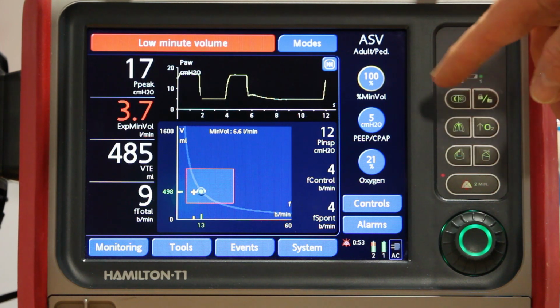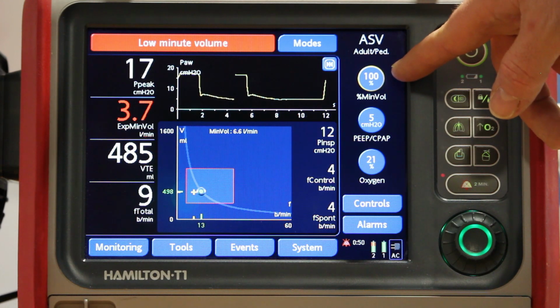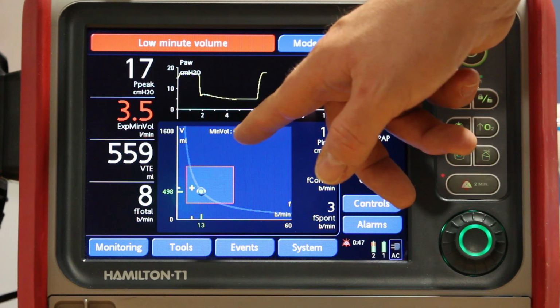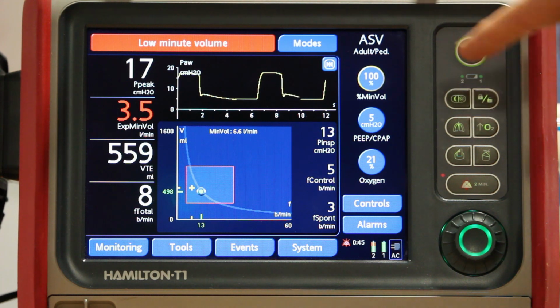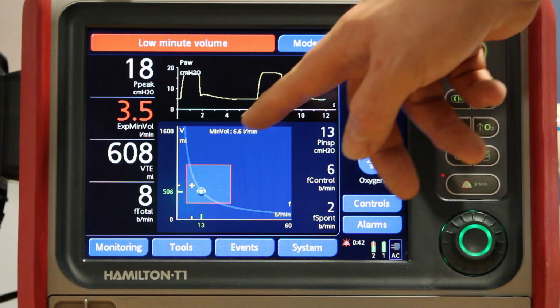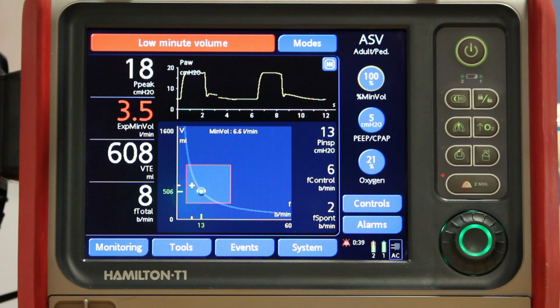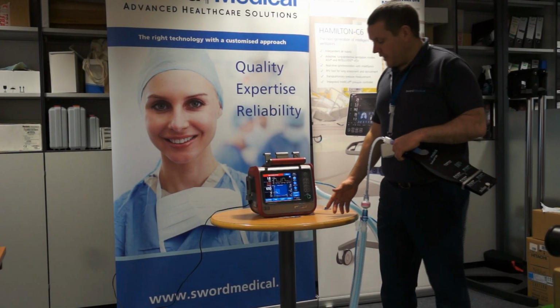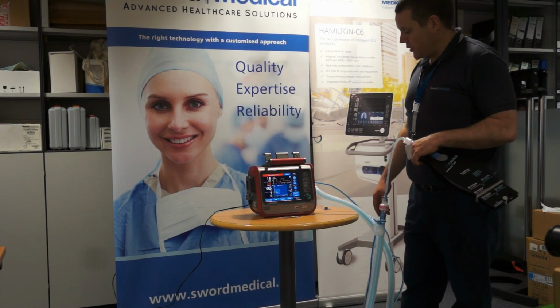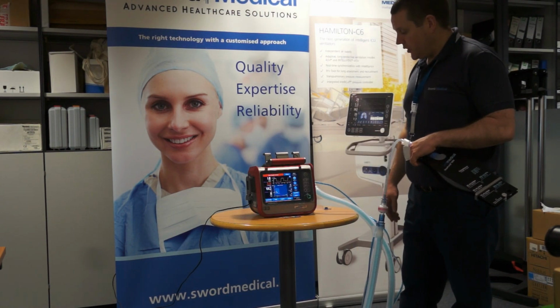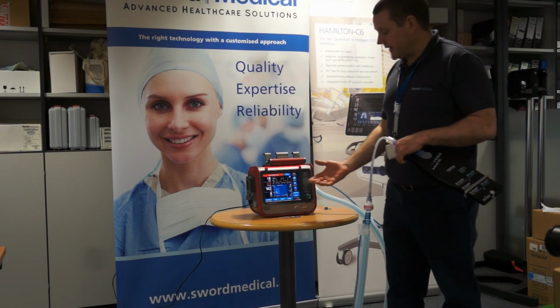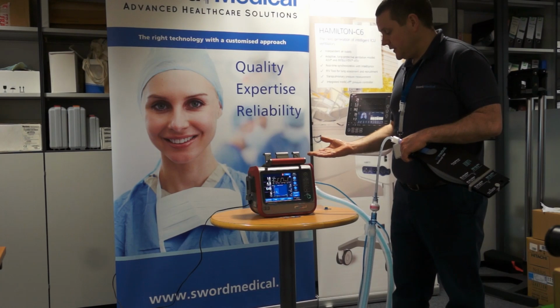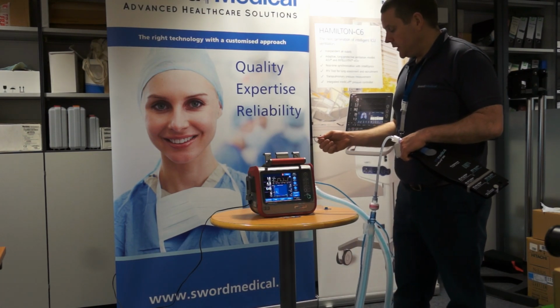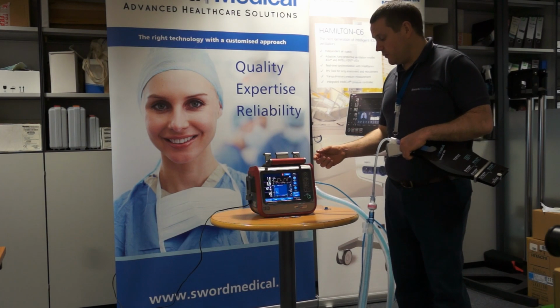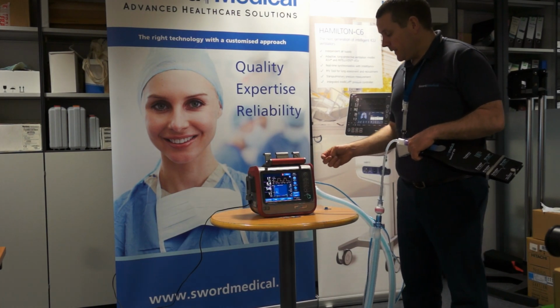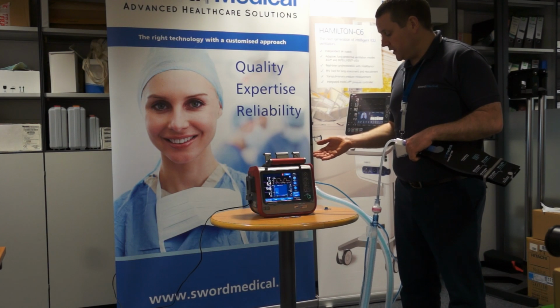The control on ASV then is we're controlling a percentage of the target minute volume. So you can see my target minute volume here is 6.6 litres per minute, and we're aiming for 100% of the 6.6 litres a minute. So if we see a rise, for example, of CO2 in our patient, normally we'd increase our rate or maybe our tidal volume a little bit, and the effect that would have overall is our minute volume would rise. So if I turn up my rate by 1, minute volume is my rate times tidal volume. So if I turn my rate up 1, my minute volume automatically goes up.